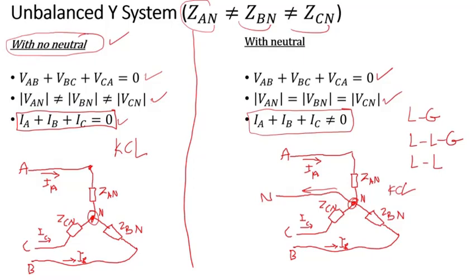And that's why the neutral wire is very important to size properly. Typically, at a very minimum, size it at least twice the phase conductor. Otherwise it could overheat and be damaged if an unbalanced situation is sustained for a long duration.